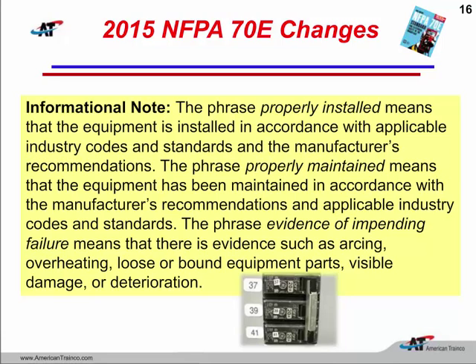Evidence of impending failure: arcing, overheating, loose parts, maybe the original equipment is not there anymore and we substituted it with something else. So when we look at this evidence of impending failure, we better make sure the equipment has all the original hardware there and that it has been properly maintained over the years, and then we can operate it normally with no PPE. Otherwise, put the PPE on and operate that equipment.